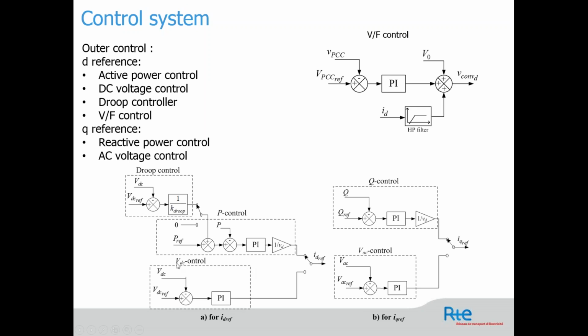The DC voltage control, of course, also has a PI loop, when the station is a VDC control. Then we have the droop control, the PVDC droop control. Basically, this is a control which will balance the DC voltage and the P control in a droop manner. And then you have a VF control. The VF control is used basically for offshore AC systems such as a wind farm or an oil platform, etc. So this is the basic idea of the VF control.